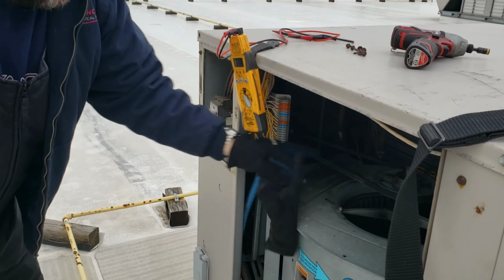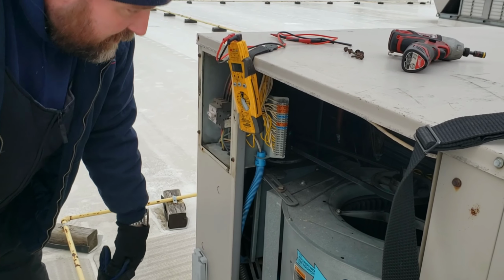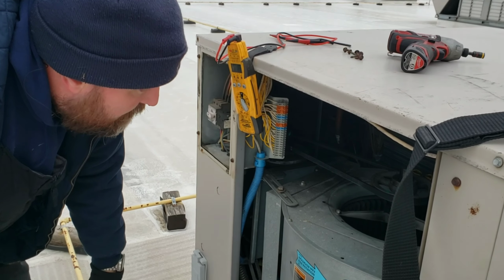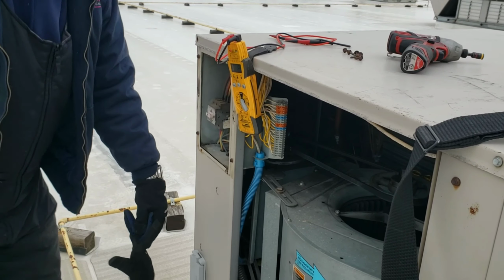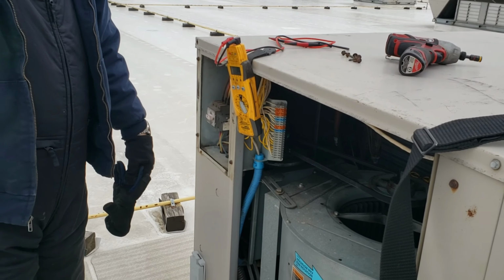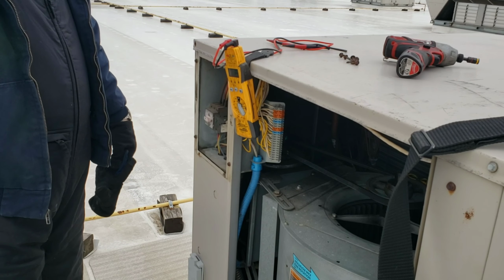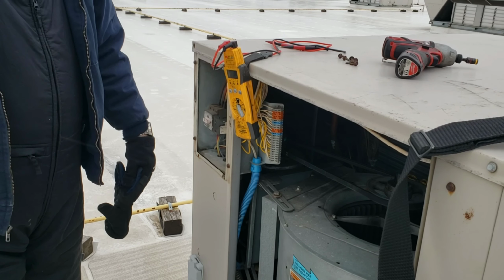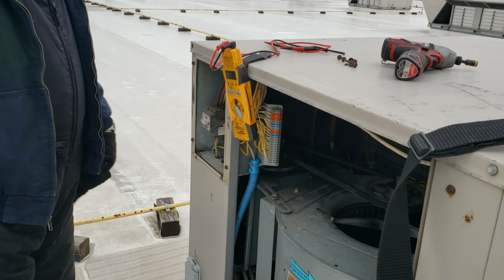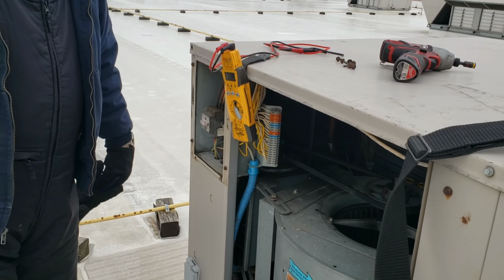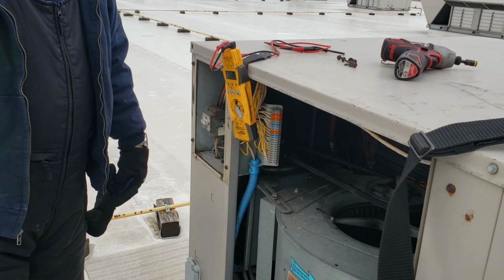We'll get this panel back on, check the belt, go through and make sure everything's lubed up like it's supposed to be, and check the condition of everything to make sure it cycles properly in heat mode. This is an older unit. I don't think it's quite old enough to start quoting for replacement yet, but once we get into it and check the heat exchanger, maybe we'll see more problems.